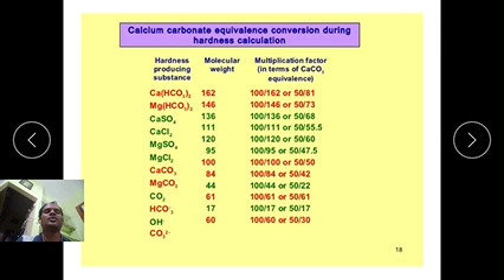Calcium carbonate equivalents present in the water equal to 204, the mass of the calcium sulfate, divided by 136, the gram molecular weight of the calcium sulfate, into 100. Then we will get 150 milligrams of calcium carbonate. The 150 milligrams of hardness is produced by the 204 milligrams of calcium sulfate per liter in the water. Similarly, different salts are there, and their molecular weights: calcium bicarbonate is 162, magnesium bicarbonate is 146, calcium sulfate 136, calcium chloride 111, magnesium sulfate 120, magnesium chloride 95, carbonate 60, and so on.